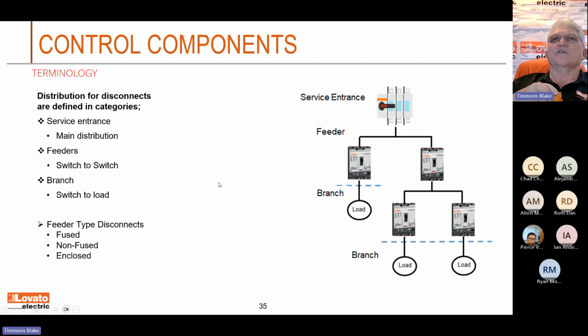So you've got some terminology you have to understand when you're doing the disconnects and feeders like this. You'll have your main distribution, then you'll have what they call a feeder, okay? And when you're dealing with disconnects and circuit breakers, a feeder is basically, the easiest way to put it, from one switch to another switch, okay? And a branch is going to be a switch to a load. So if you've got some kind of a switch that you want to just turn a motor off and on, that's going to be a branch. If you've got something feeding your control panel that's going to feed another switch, that's our feeders. They'll come in different flavors, fused, non-fused. You'll have some enclosed ones.